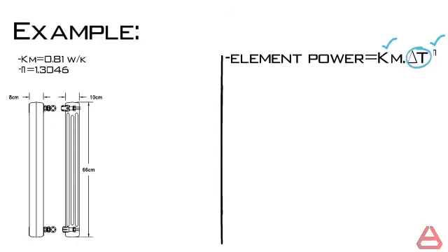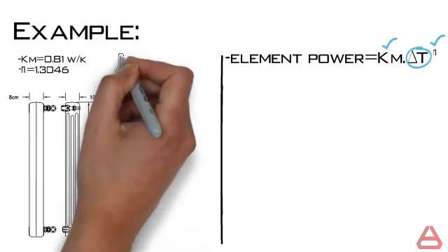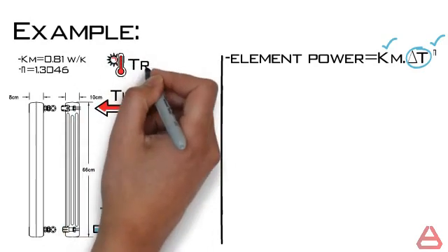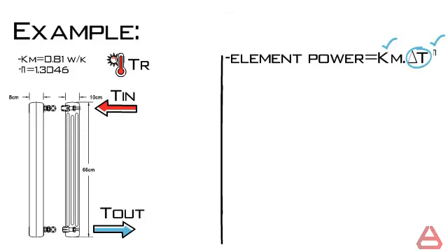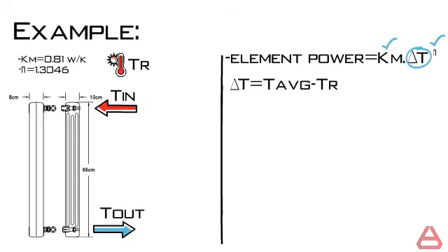Delta T on the other hand is not a function of the radiator material or geometry, but actually is a function of the in-out temperatures of the radiator and the required room temperature. It is equal to the difference of the average of T in and T out and the room temperature.